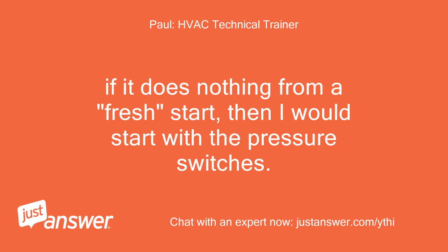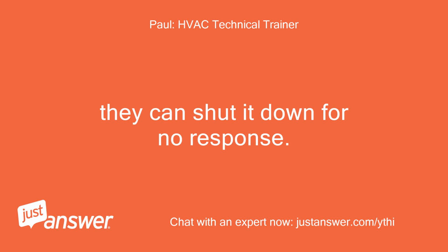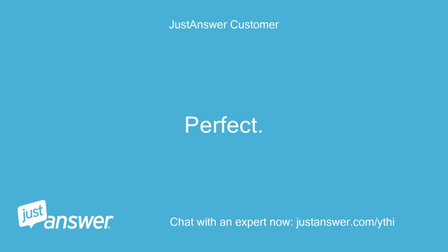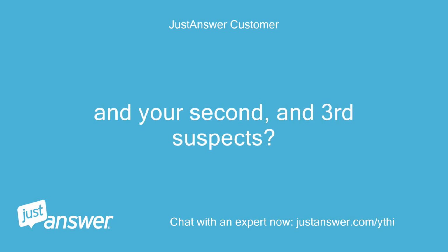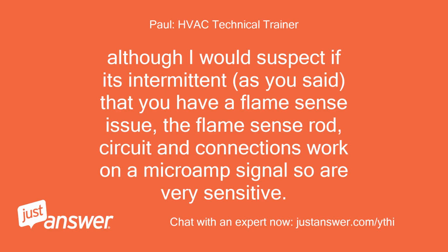If it does nothing from a fresh start, then I would start with the pressure switches. They can shut it down for no response. Perfect. And your second and third suspects? Although I would suspect, if it's intermittent as you said, that you have a flame sense issue. The flame sense rod, circuit and connections work on a microamp signal, so are very sensitive.